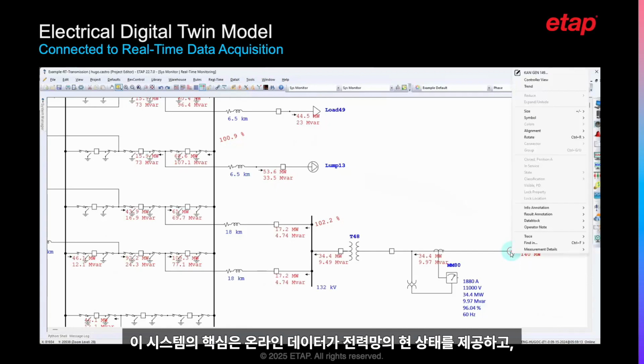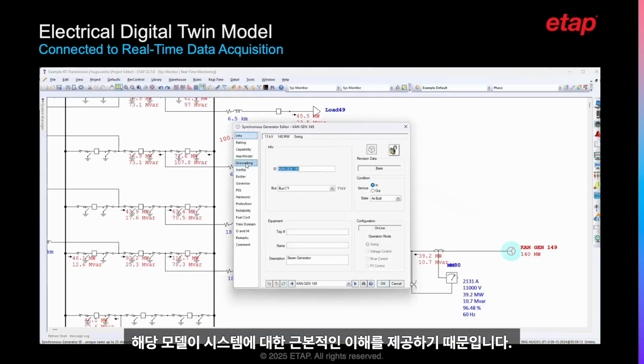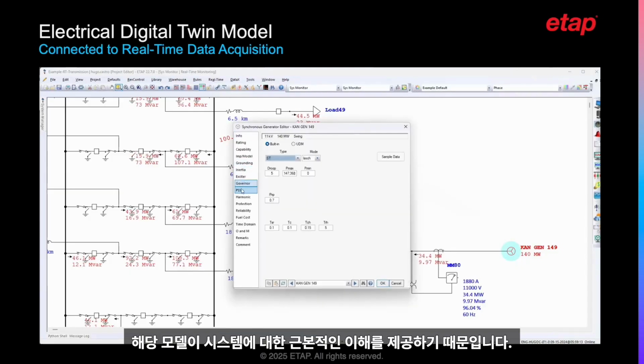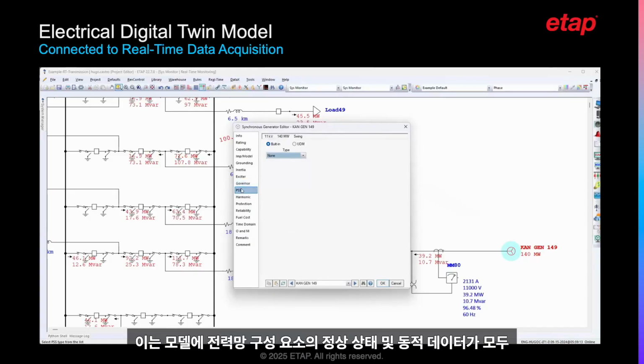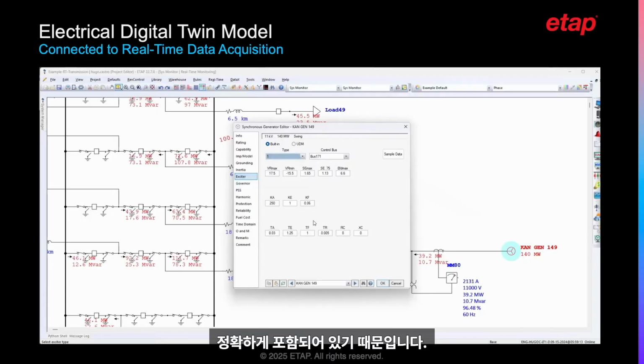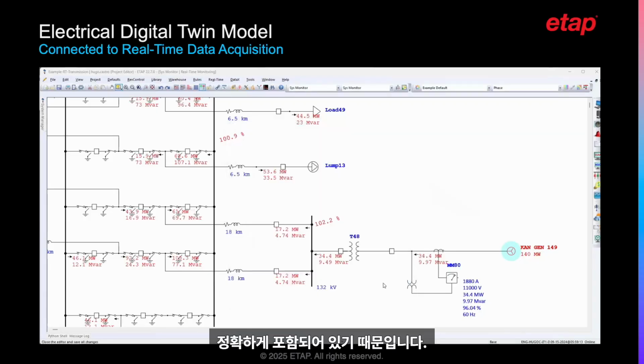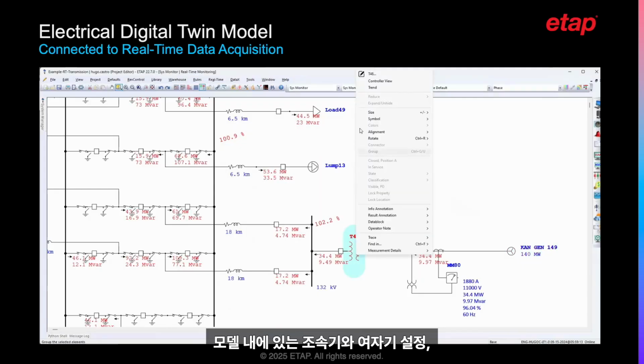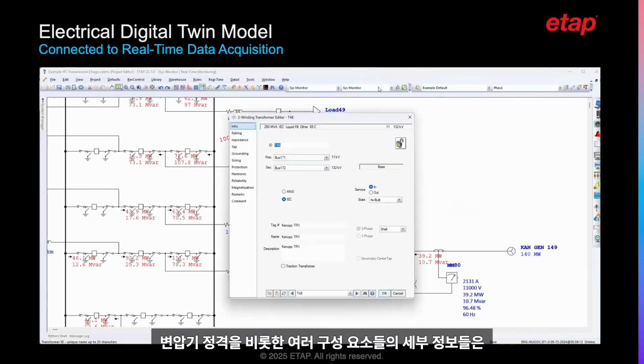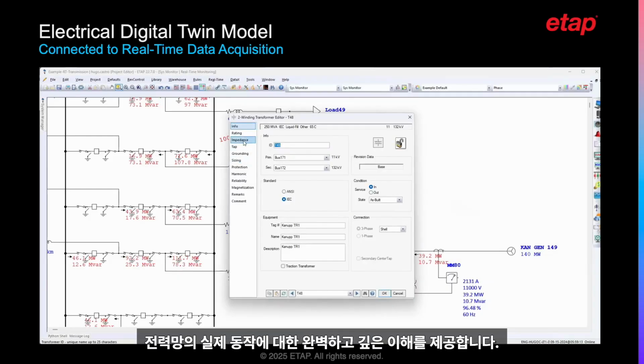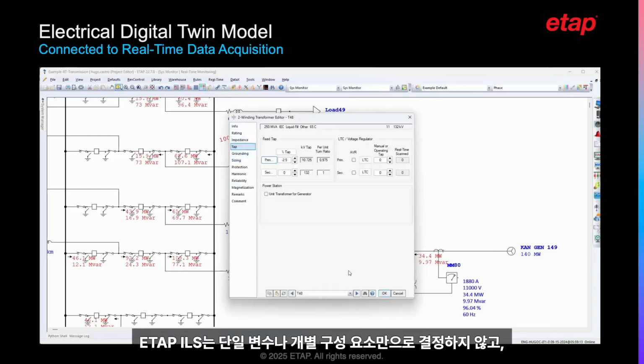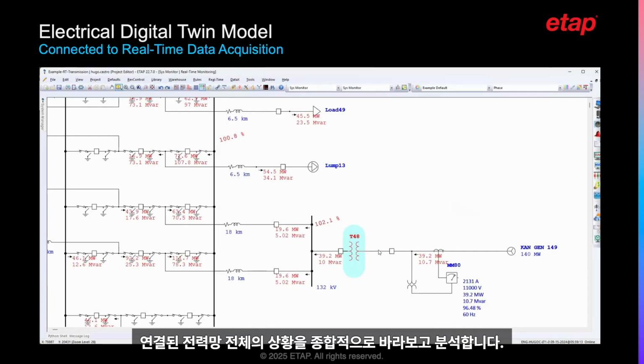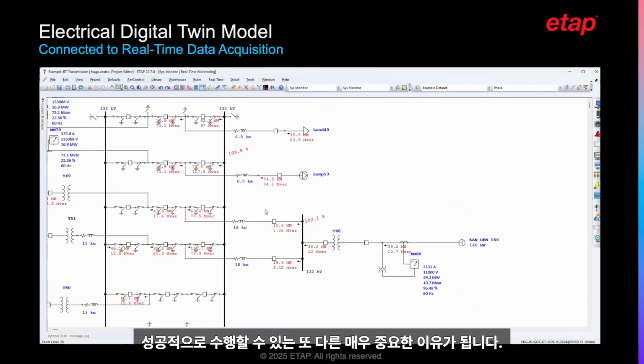The intelligence of this predicted system response is that the online data provides the current conditions of the network, and the model provides us with the understanding of the system. This is due to the fact that the model contains steady-state and dynamic data of the components in the network. The governor and exciter settings that can be found in the model, the transformer ratings, as well as other components, give a complete understanding of the network's behavior. Note that ETAP ILS is looking at the entire network instead of at a single parameter or component to make decisions. This is also another important factor in why ETAP ILS can perform optimization of the entire network.